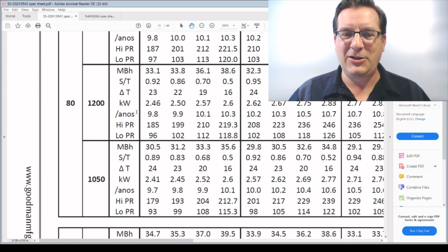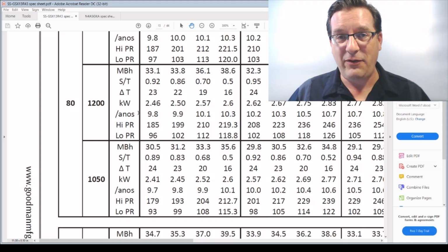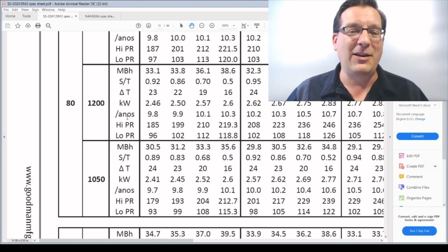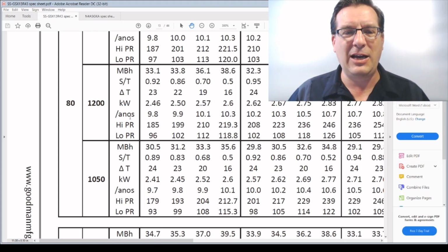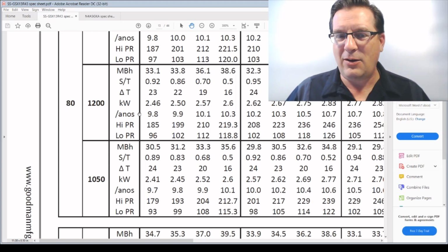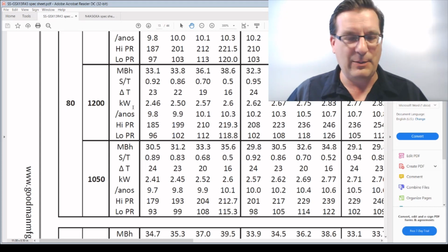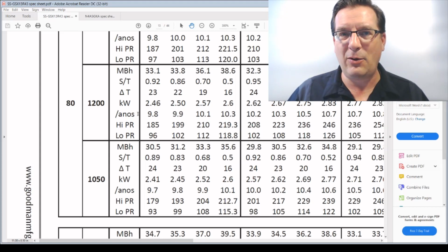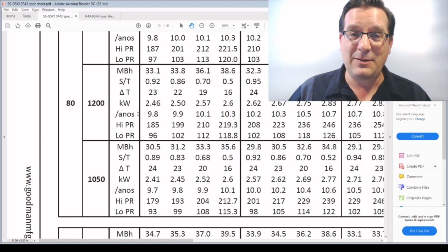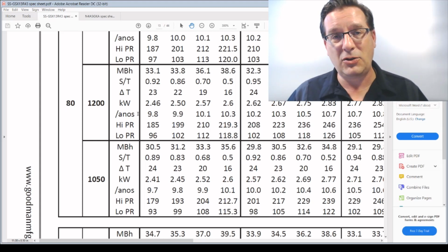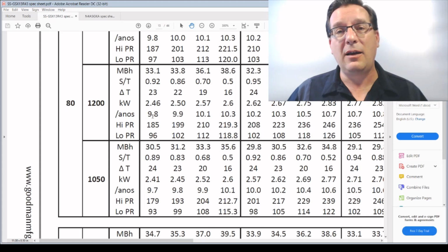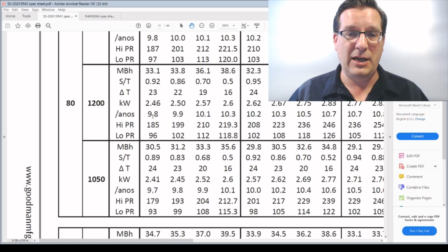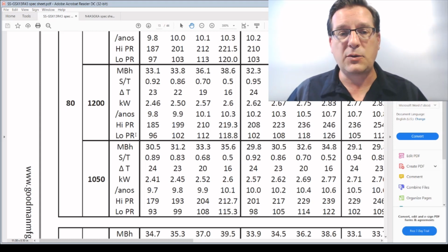This next one I get a chuckle out of because the more you look at specification sheets, the more you're going to find problems. And this one says "ANOS," which if it had an accent on it, it might be a Spanish word, but it is actually a typo. It's supposed to say amps. And this means how many amps will the condensing unit draw under these conditions. There again, that will change with the performance as it changes. High PR is high pressure, low PR is low pressure. So that's what we're going to be looking at.